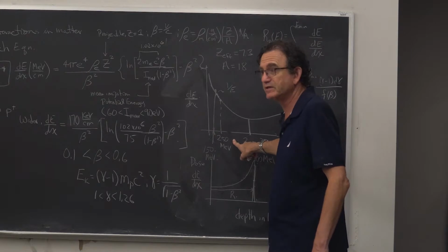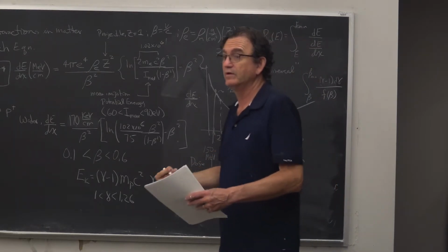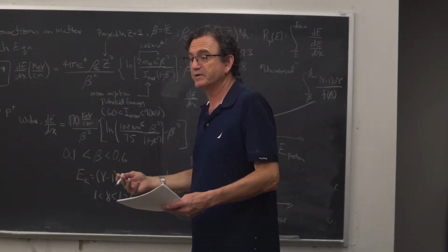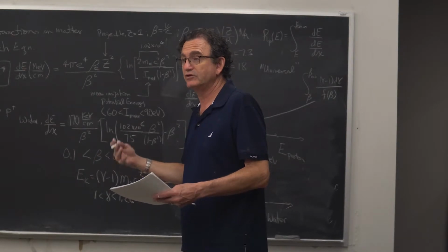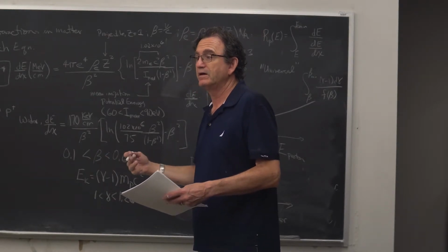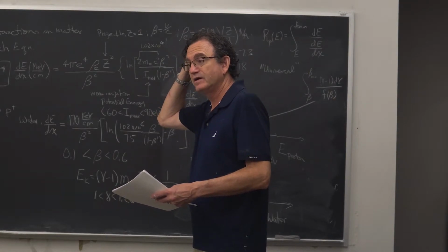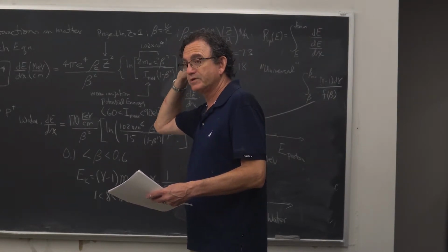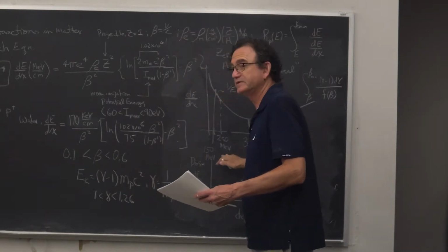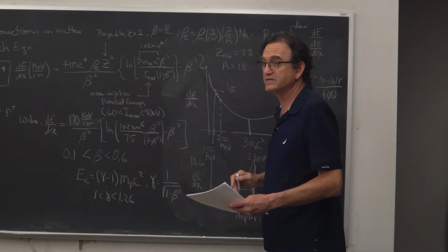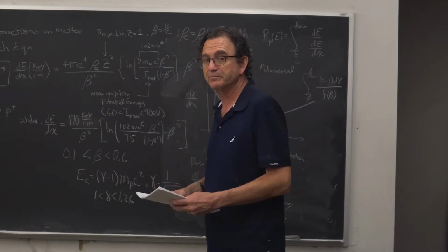This is sort of the upper limit that's available in proton therapy clinics. It does cost a lot of money to go to higher energies. So unless there's a very strong incentive, we typically don't go over this number to help keep the cost down. It's the cost of the accelerator and the beam lines and so forth.